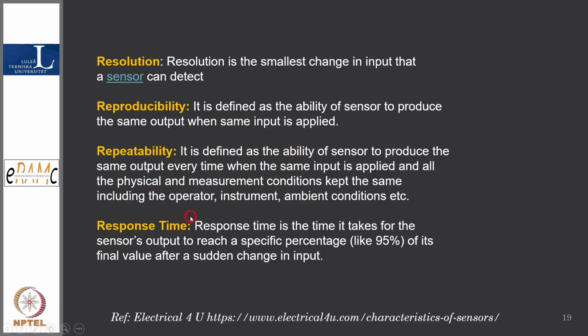And this is, of course, response time, or time constant as I put it. How it should be: the response time should be such that the time it takes for the sensor's output to reach a specific percentage of its final value after a sudden change in the input. That means it should respond pretty well to the changing condition, and it should reach 95% very efficiently. It should not take time, and it should not have its own time constant for reaching the true value.